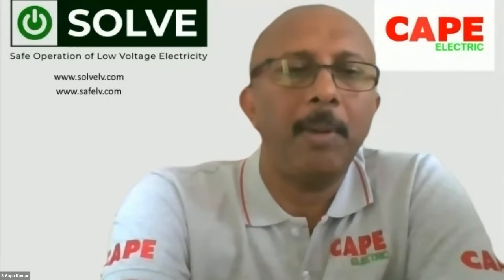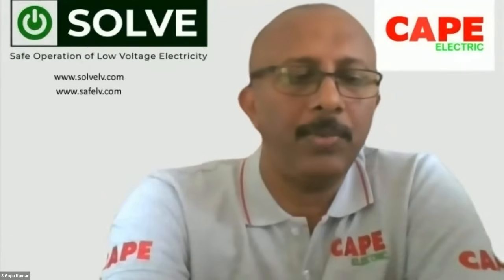For example, in Europe, let's say in Belgium, for residential purposes, the frequency of periodic verification is about 25 years. Initially, when you start the electricity in your house, you do the verification. Then the next verification is after 25 years. That means the life of the installation is at least double that. So I would say the answer is 40 years in a properly designed, installed and verified installation. If these three things are not carried out, probably 5 years.